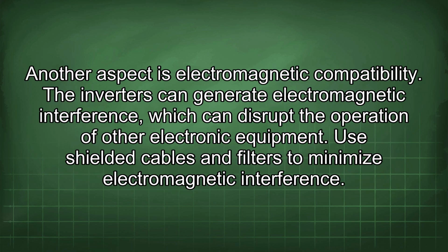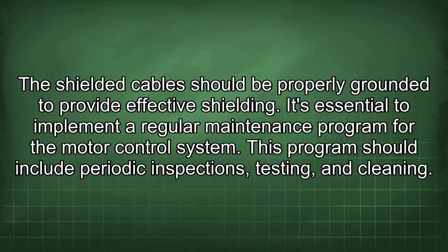Another aspect is electromagnetic compatibility. The inverters can generate electromagnetic interference which can disrupt the operation of other electronic equipment. Use shielded cables and filters to minimize electromagnetic interference. The shielded cables should be properly grounded to provide effective shielding.